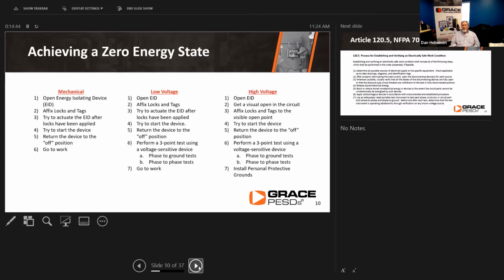Moving into high voltage, very similar to low, with the addition of get a visual open in the circuit. So look for visible blades, verify that they have opened up, and then again, you're going to apply your locks and tags, try to start the device, return the device to the off position, and then perform your 3-point test using voltage testing devices. And you're going to do phase to phase and phase to ground tests, and make sure that everybody around the work, as work starts, installs their personal protective grounds.